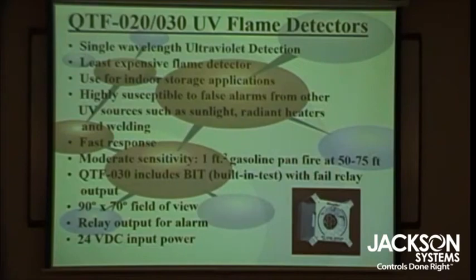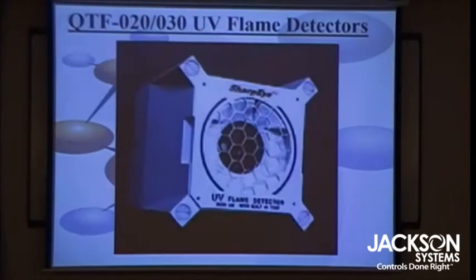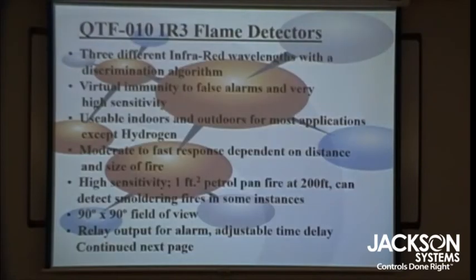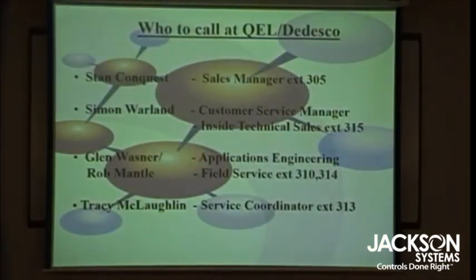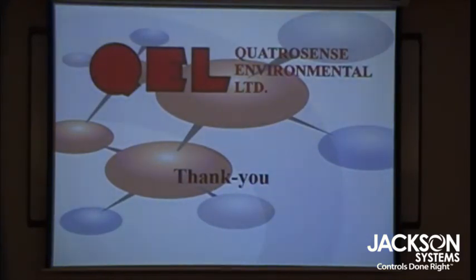Flame detectors, this is really for military applications. These things are pretty neat in that it'll detect the flame 200 feet away for the top of the line one, usually connected to your fire alarm system. These are used in aircraft hangars, in jet fuel storage facilities and things like that. If there's any spontaneous ignition from combustible fuels, this will pick it up. You can even have CCTV cameras to look at the fire and things like that. And that's it for that particular part.